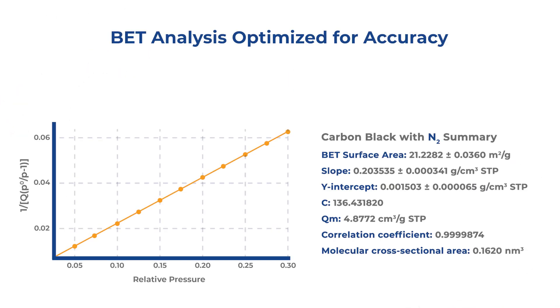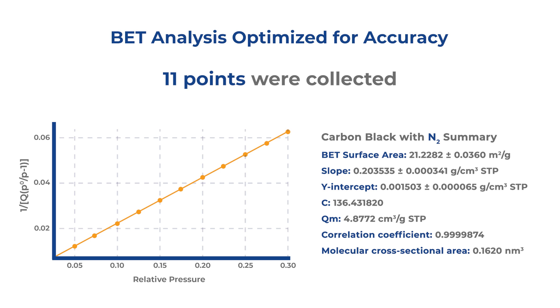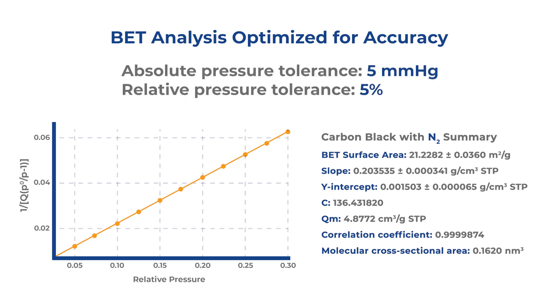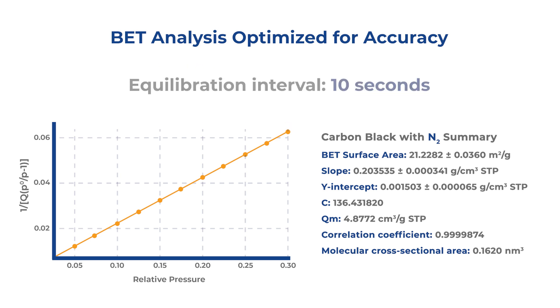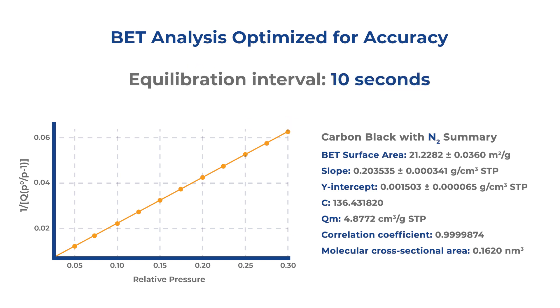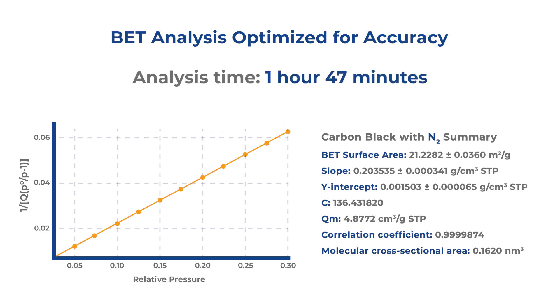Now let's look at some examples. Here's the first example with a typical BET run with analysis conditions optimized for accuracy for a carbon black sample. The pressure tolerances were set as default for a nitrogen isotherm, with measuring the free space and saturation pressure, and setting the equilibration interval at 10 seconds. The analysis took one hour and 47 minutes under these conditions.